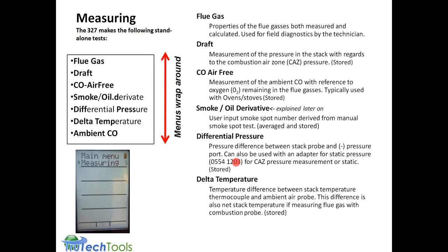Delta pressure, or excuse me, delta temperature is the difference between the stack probe and the thermocouple. This is also sometimes called net stack temperature. It's used automatically in the flue gas mode, but it's also available to be used if you want to measure, say, a difference in a hydronic heating system between the two temperatures, or the temperature rise over a piece of equipment, or temperature fall over a piece of equipment.